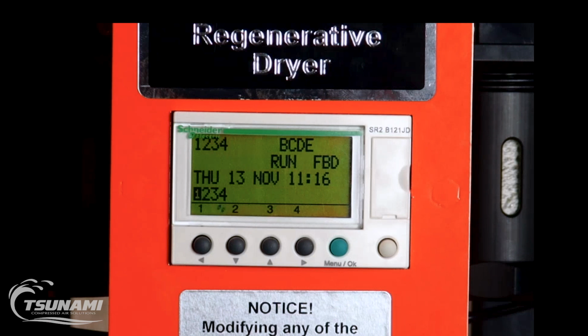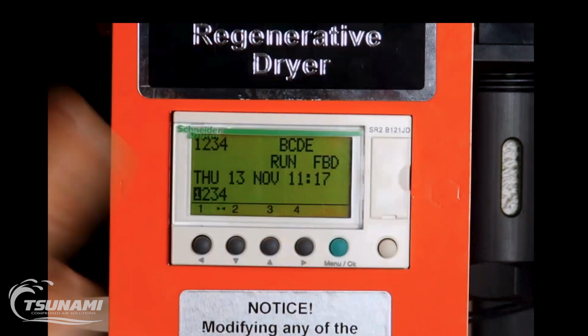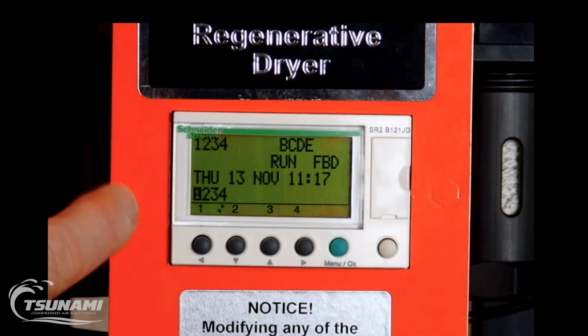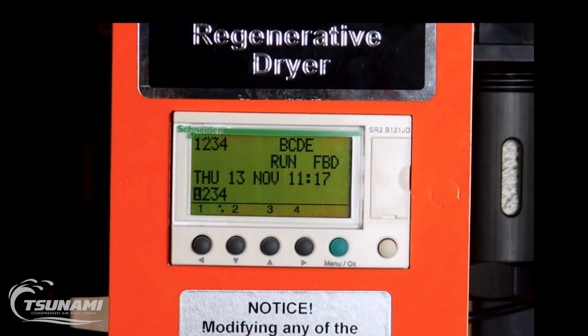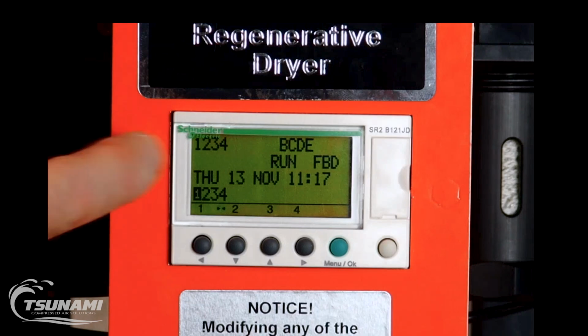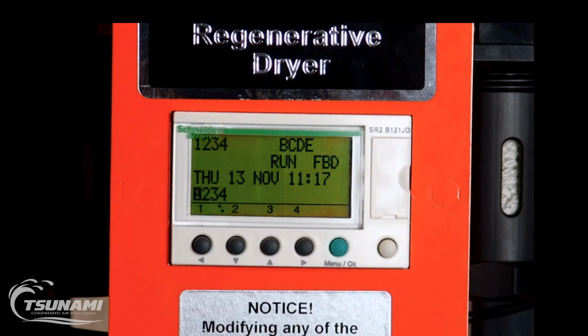The second thing is, now that we know that this is the correct program, if this was an older version, it might say 10 horsepower program selected, which would be this 2-tower dryer that this PLC is currently mounted on. To explain a little bit about the control itself, obviously it has the date and time that you can see. It tells us that it's in a run mode. If we were to stop the program, which I will show you later, that will say stop there.